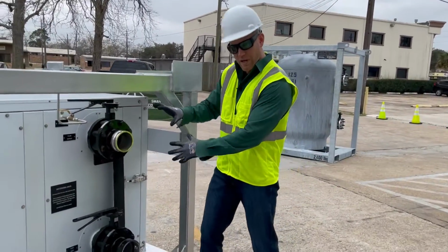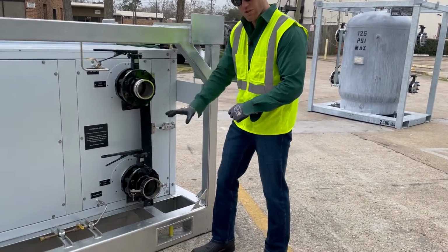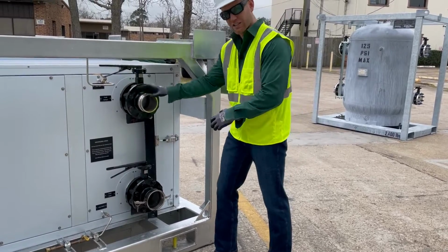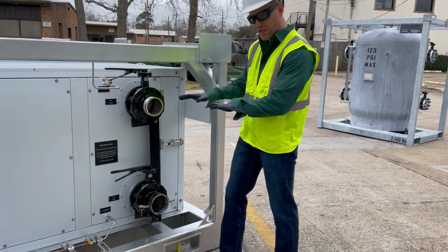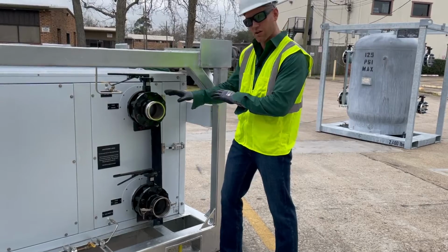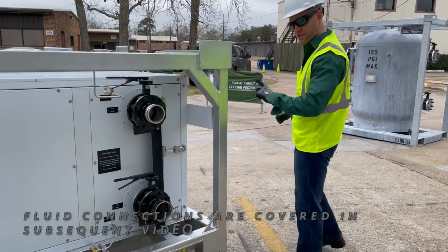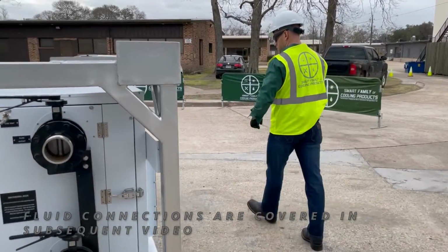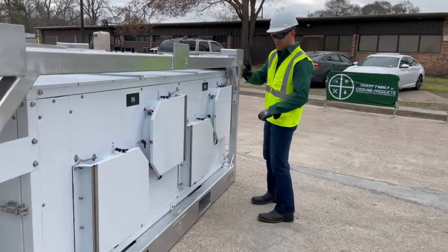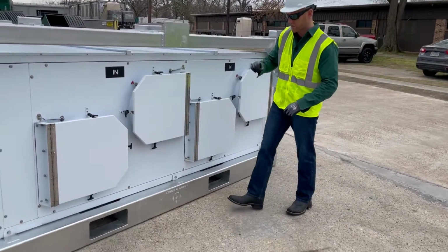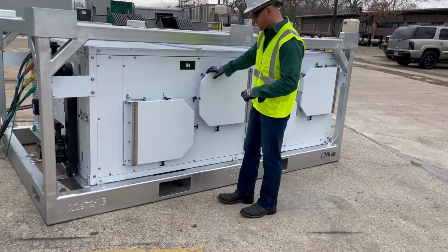You'll see as we walk past our fluid connections here, nothing's hooked up. We talk about connecting the unit, the fluid side, and filling it with fluid, water or propylene glycol, in another video, okay? So pay attention to that video. But step number two is making sure we have a clean and clear air path for this air handler. So we're going to open up our inlet connections.